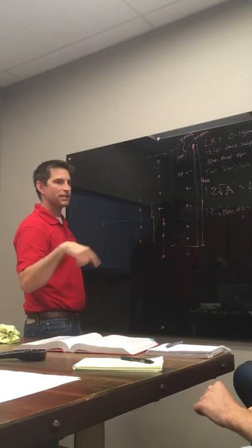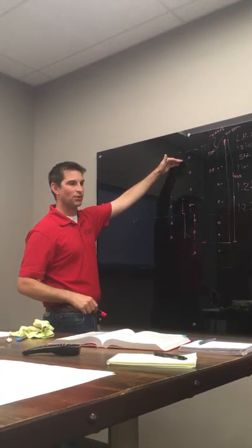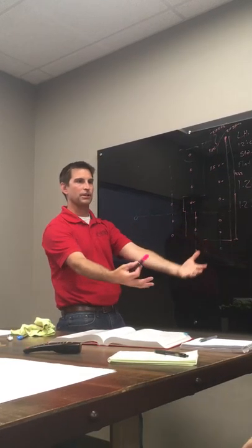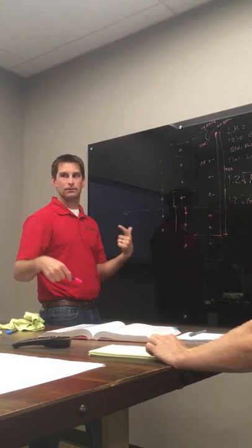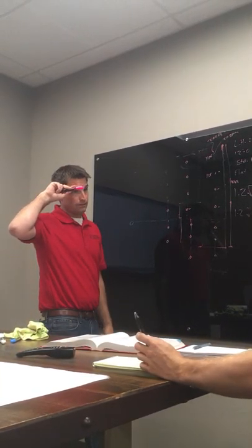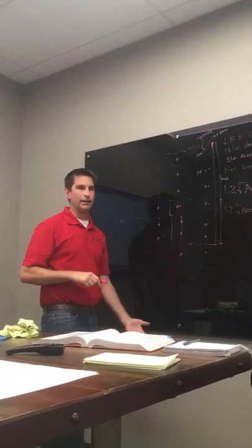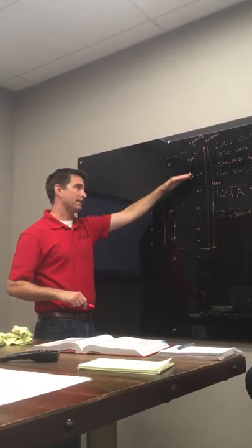It's kind of confusing for a lot of people. So you want to say, well, that's further away. But it's all based off your most demanding head and it's working its way backwards. And then all the other heads overflow. So it's how much they would actually use versus how much they need after you use the one that needs the most. You've got to get at least that much to that one, in order to get that, then these are all going to flow.